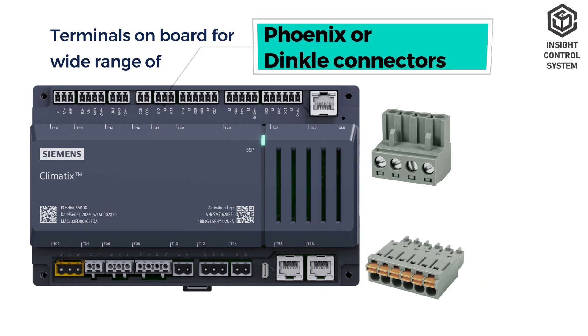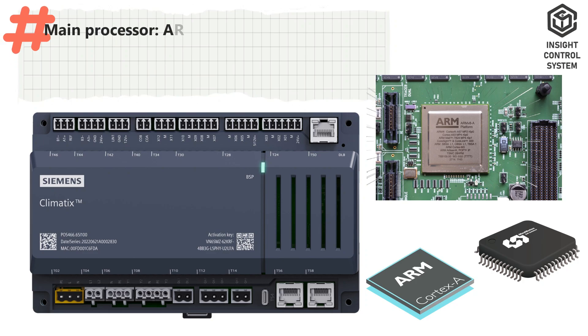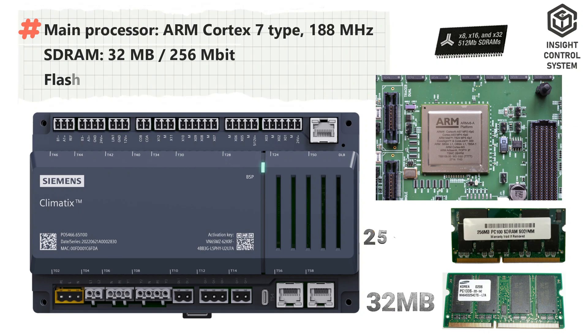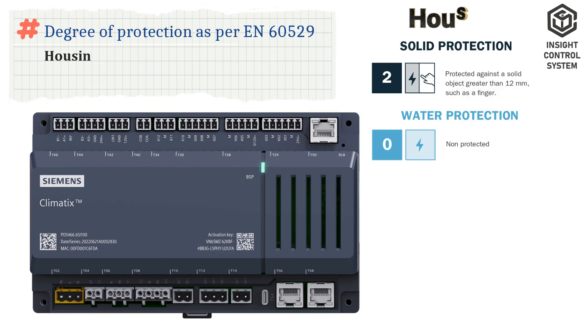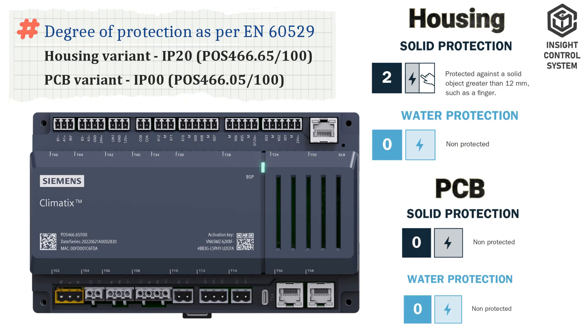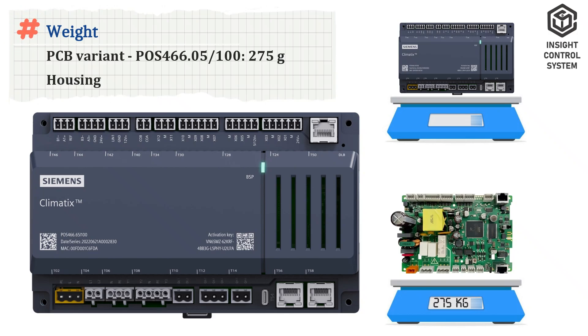Terminals on board support a wide range of Phoenix or Dinkle connectors. The main processor is ARM Cortex-7 type at 188 MHz. SDRAM is 32 MB or 256 Mbit, and flash memory is 16 MB or 128 Mbit. The degree of protection for the housing variant is IP20 and the PCB variant is IP00. Weight for the PCB variant is 275 grams, and for the controller with housing variant is 427 grams.